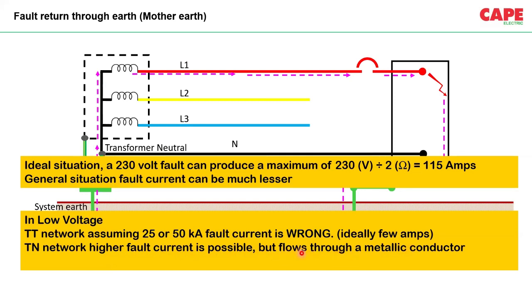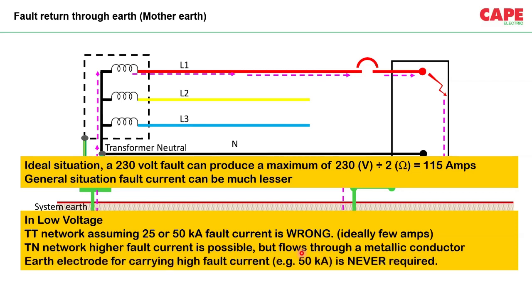So in a TN network, the size of the metallic conductor fault return path has to be large enough so that that particular conductor is not damaged and it is not creating any fire accident. So, in conclusion of this slide, an earth electrode for carrying high fault current, say for example 50 kiloampere, is never required for a low voltage application. Not even for low voltage, even for a high voltage application, this is never going to happen.